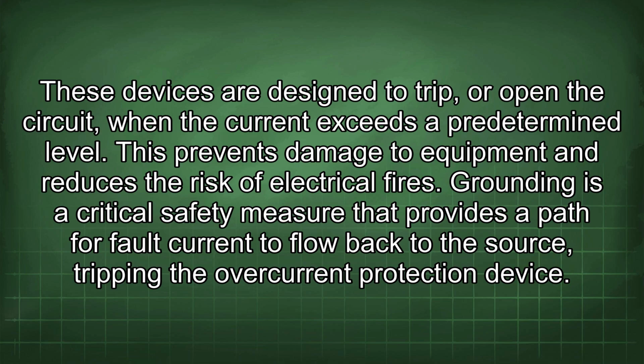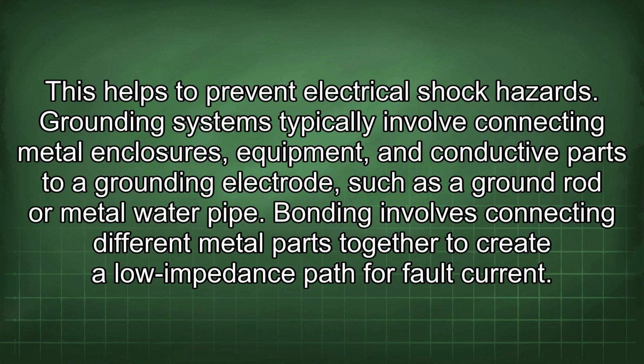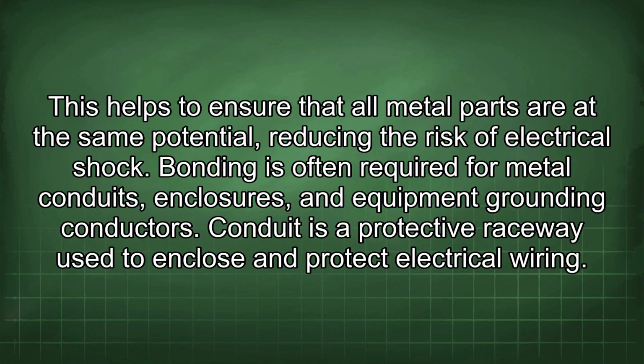Grounding is a critical safety measure that provides a path for fault current to flow back to the source, tripping the overcurrent protection device. This helps to prevent electrical shock hazards. Grounding systems typically involve connecting metal enclosures, equipment, and conductive parts to a grounding electrode, such as a ground rod or metal water pipe. Bonding involves connecting different metal parts together to create a low impedance path for fault current. This helps to ensure that all metal parts are at the same potential, reducing the risk of electrical shock. Bonding is often required for metal conduits, enclosures, and equipment grounding conductors.